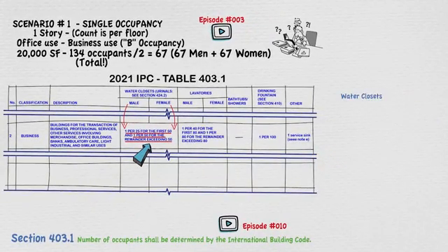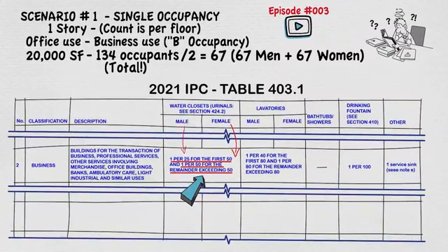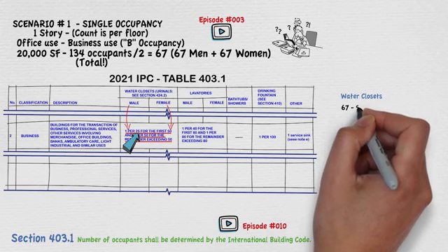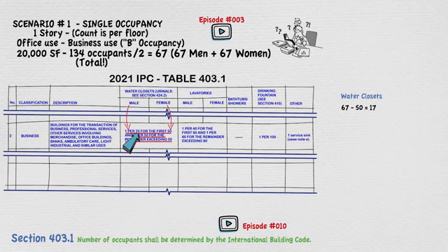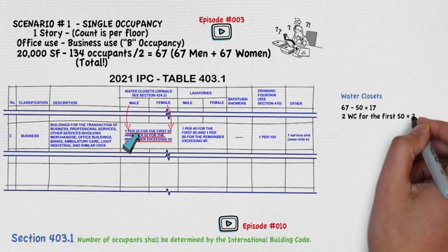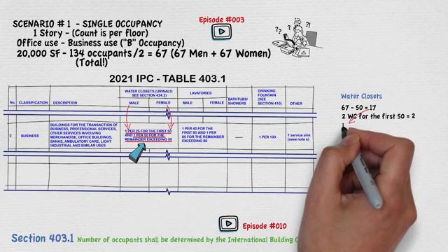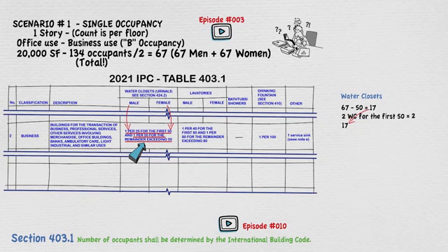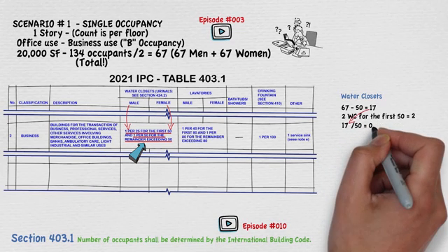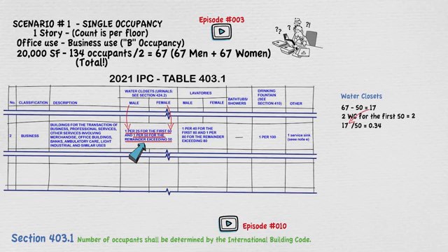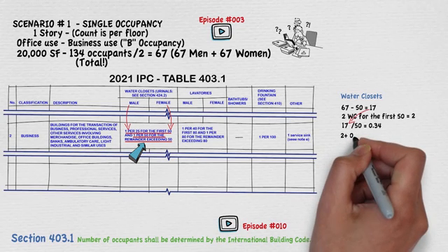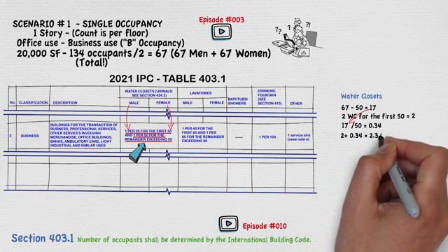Let's start with the water closets. Water closet count is the same for men and women. The requirement states one water closet per 25 occupants for the first 50 occupants. Since we have 67 occupants, we subtract 50, meaning we need 2 water closets for the first 50. Then it's one fixture per 50 of the remainder. The remainder is 17 occupants: 17 divided by 50 equals 0.34. Adding 2 plus 0.34 gives a total of 2.34 water closets.